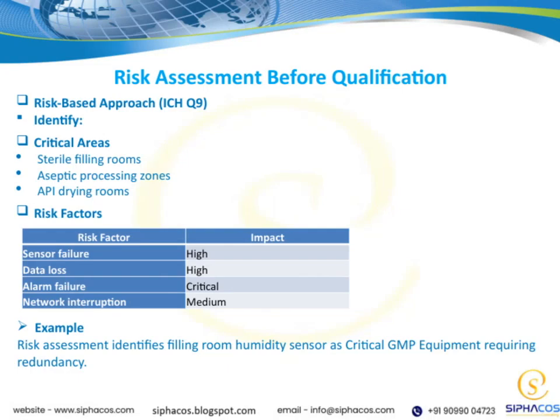Let's look at a practical example of how risk assessment works in a GMP environment. Here, a humidity sensor in a filling room is identified as critical equipment, meaning it needs redundancy to avoid failures. The table breaks down risk factors like sensor failure and alarm failure, showing their impact levels. This approach helps us focus on the most vulnerable points in critical areas, like sterile filling rooms and aseptic zones, ensuring we manage risks where they matter most.